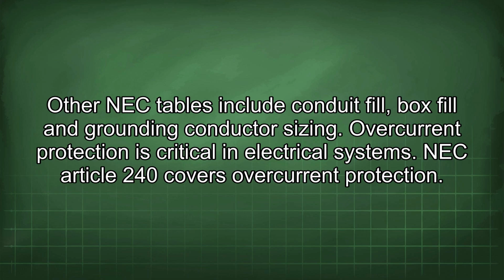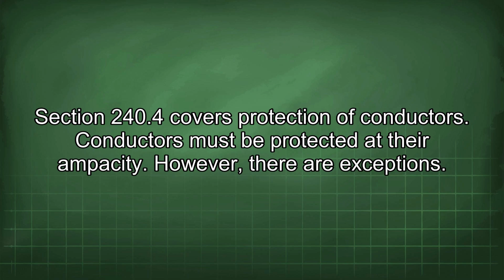Overcurrent protection is critical in electrical systems. NEC Article 240 covers overcurrent protection. Section 240.4 covers protection of conductors. Conductors must be protected at their ampacity. However, there are exceptions.